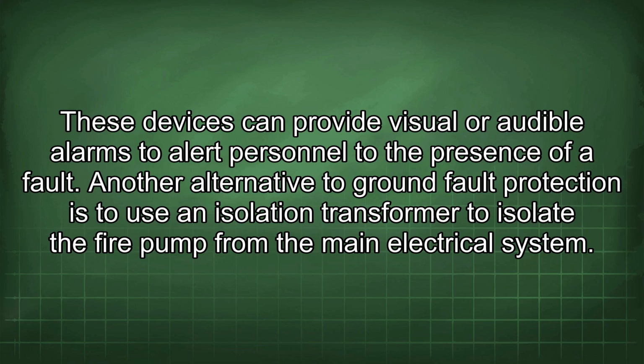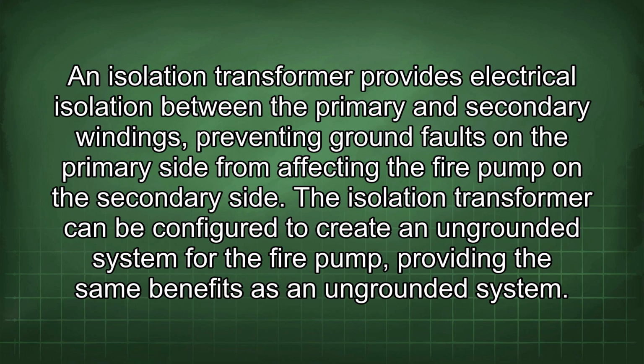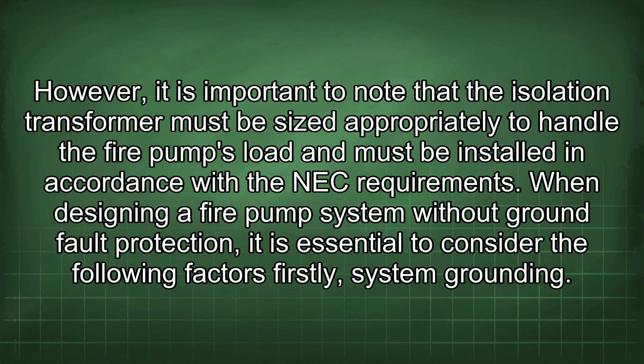Another alternative to ground fault protection is to use an isolation transformer to isolate the fire pump from the main electrical system. An isolation transformer provides electrical isolation between the primary and secondary windings, preventing ground faults on the primary side from affecting the fire pump on the secondary side. The isolation transformer can be configured to create an ungrounded system for the fire pump, providing the same benefits as an ungrounded system. However, it is important to note that the isolation transformer must be sized appropriately to handle the fire pump's load and must be installed in accordance with the NEC requirements.